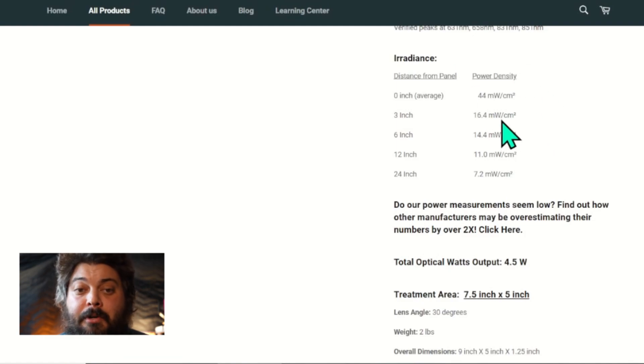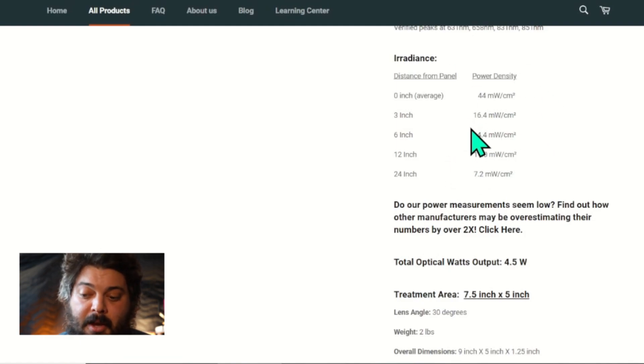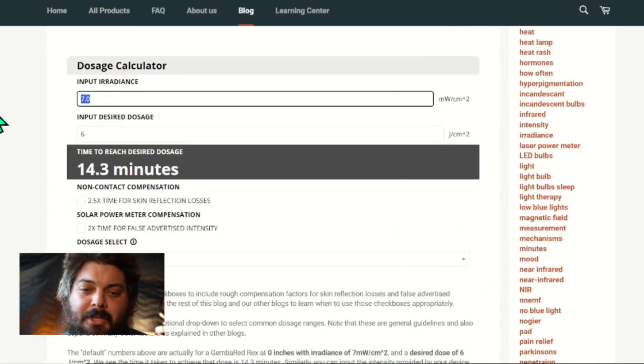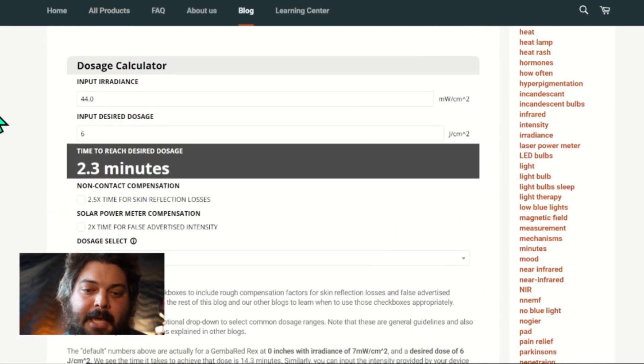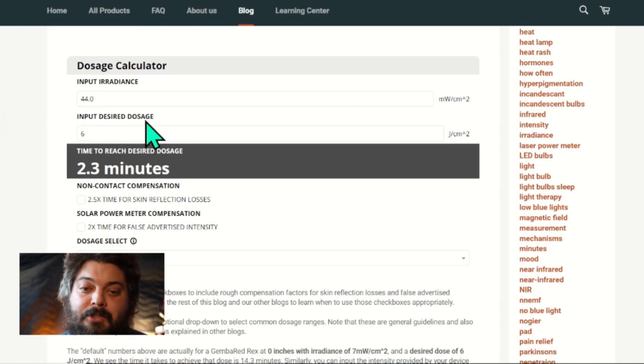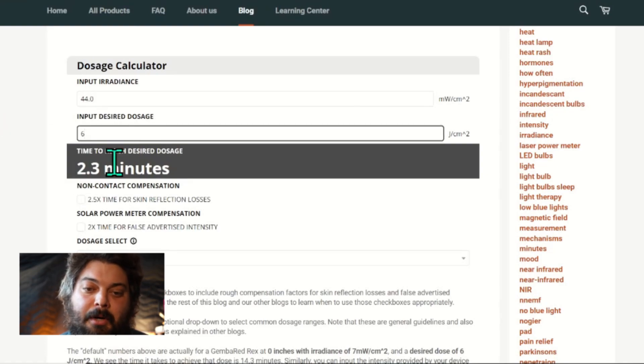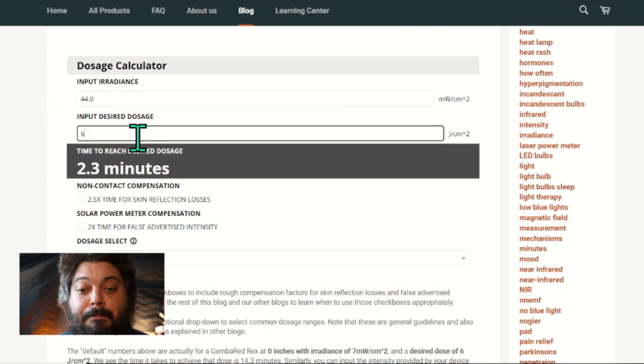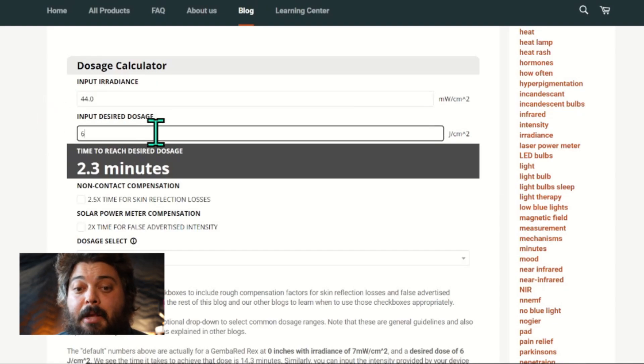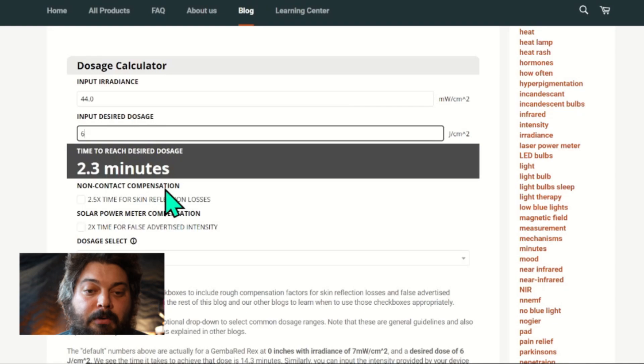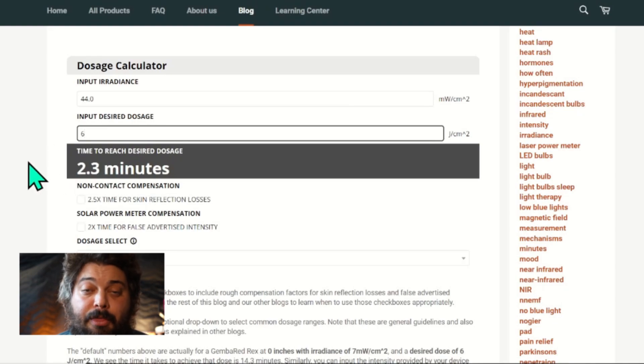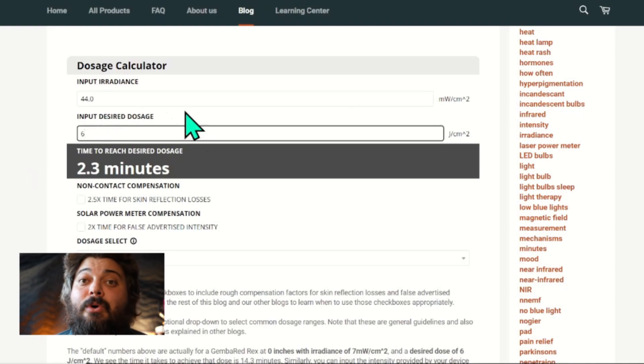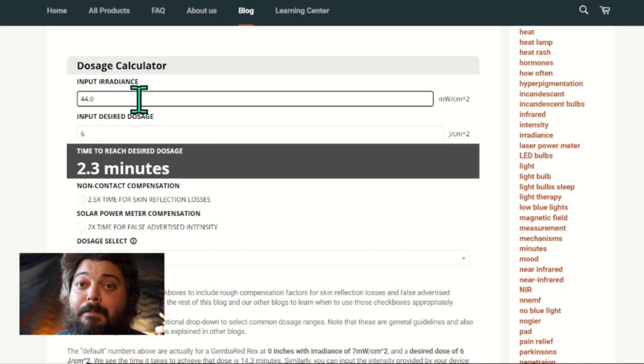Then we go over to the dosing calculator, and that's what we put in: 44. And we press Enter, or if you just click off of it, it'll automatically update the minutes. As soon as you change a number and then click something or press Enter, it'll update the calculation and tell you how many minutes. So if we want 6 joules per centimeter squared with the Gemba Red Vector on the skin, you need to use it for 2.3 minutes. So that's it, pretty straightforward.